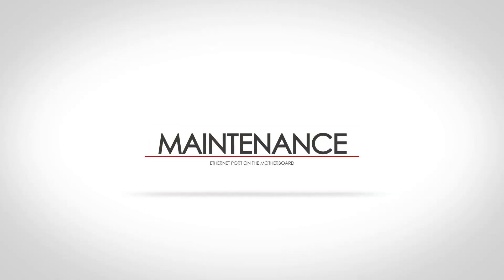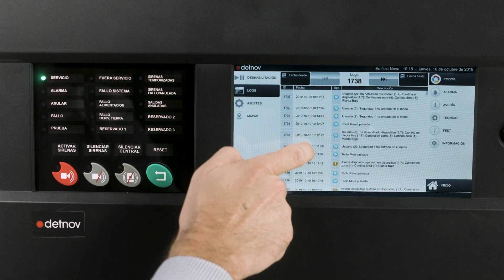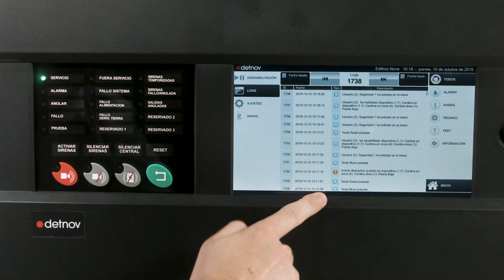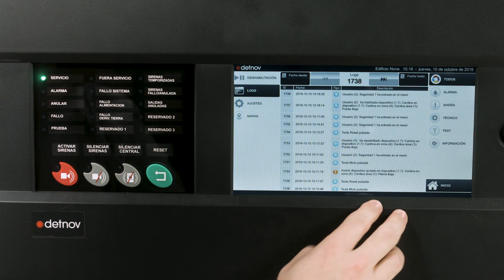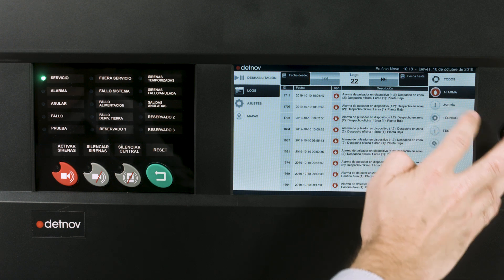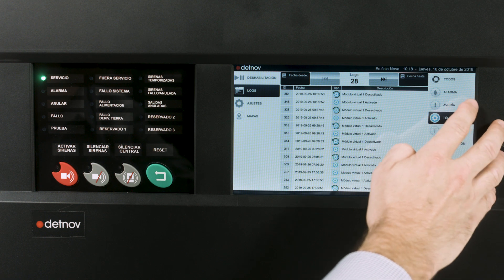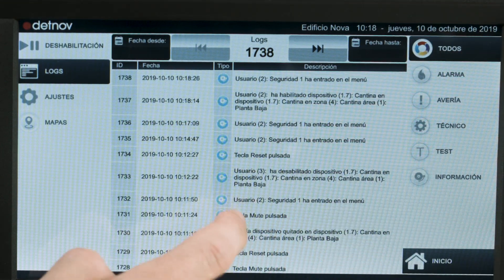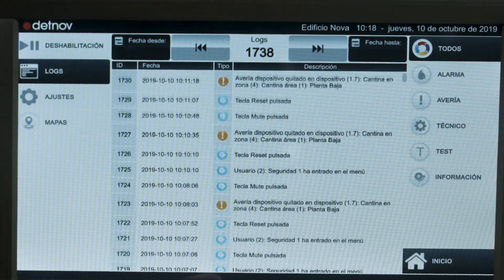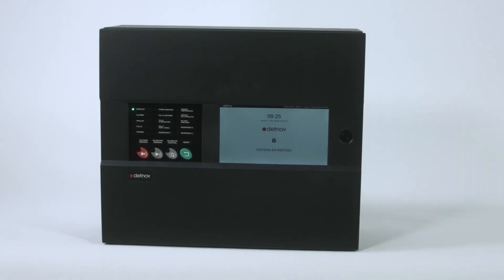Maintenance. Maintenance technicians can carry out scheduled tasks visually, thanks to specially designed displays on the 10-inch touchscreen. Dirty sensors, disabled devices or any other incident in any device in the fire detection loops can be located at a glance. The Ethernet port on the motherboard provides an endless range of options, most notably remote programming, which can result in savings in call-out costs for start-up and maintenance staff.